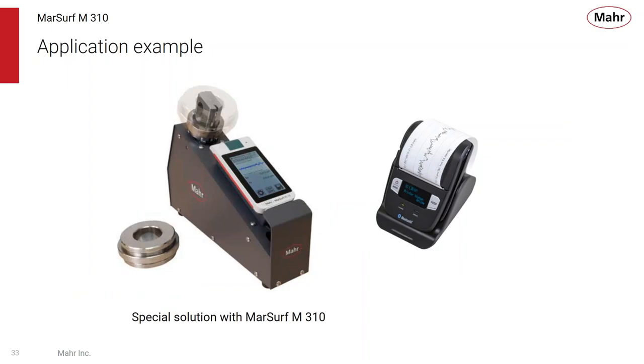One of the great things about the M310 and its remote control facilities, and the ability to remove the drive, is now you can build the drive system into a lot of custom application solutions where it's dedicated to the measurement. The operator doesn't have to try and position the probe into a small hole or deep into a bore. We can come up with special applications to make it a lot easier for the user.